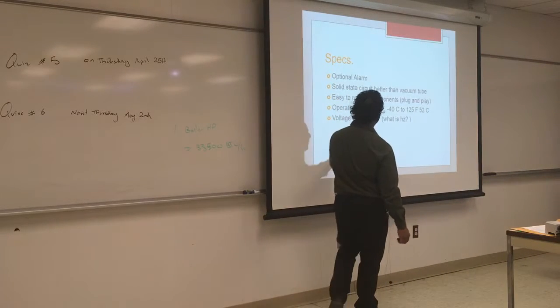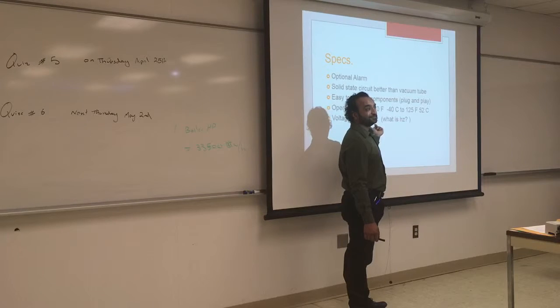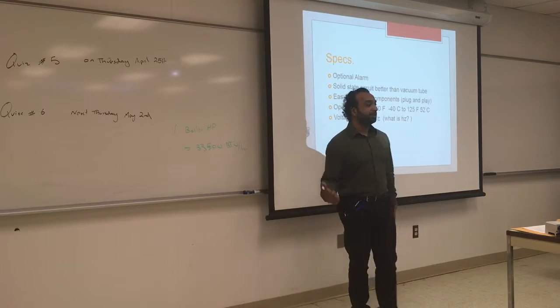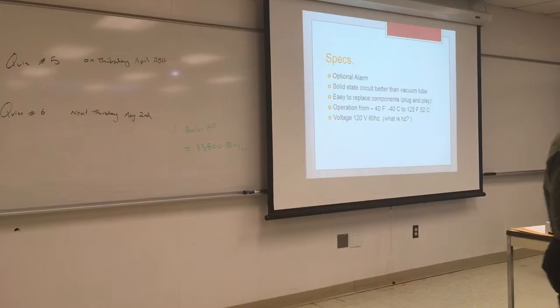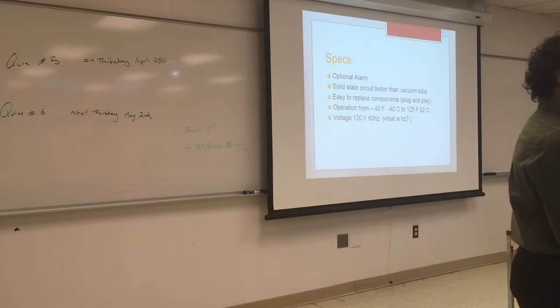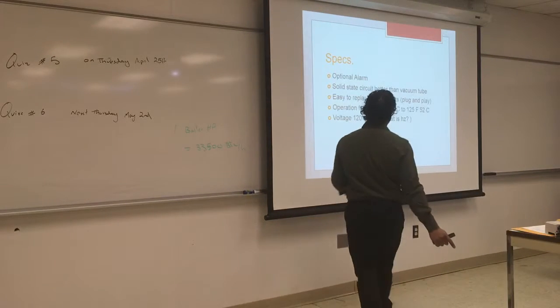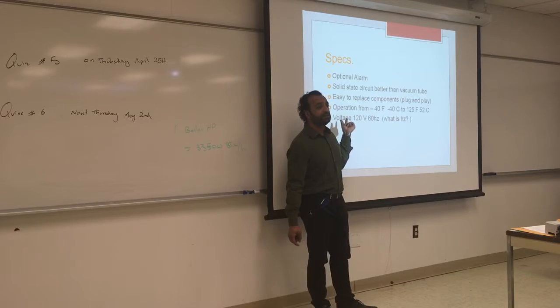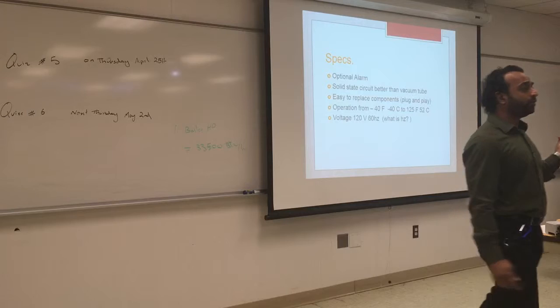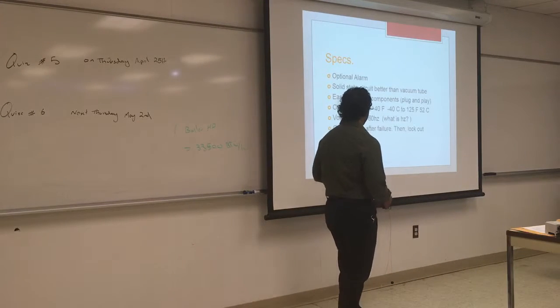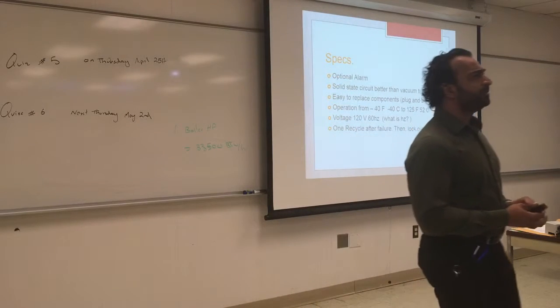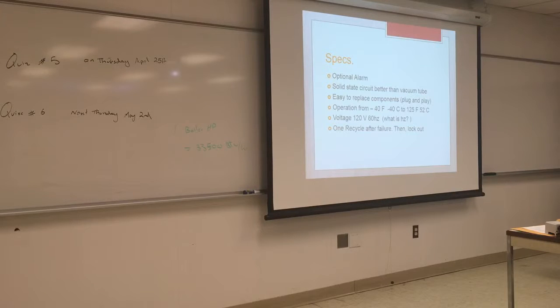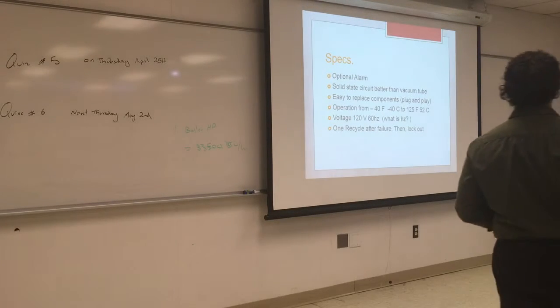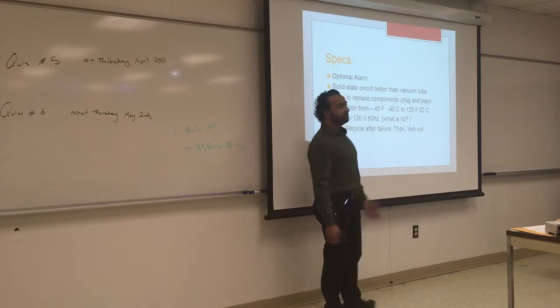The voltage is 120 volts, and I hope by now you know what hertz is. How many cycles? Yeah, it's frequency. And what frequency do you get in the residential? No, we're supposed to be getting like 60 or 59. But it can be within 10% of that in either direction, it still works, right? No, these are actually more sensitive. I don't think it's going to be more than 10%. These controls, because they're electronic and they have a lot of semiconductors, are very sensitive to frequency. If you change the frequency, it might not work properly. So we want it to be 60 hertz, and I think whether it's 10% or maybe less than that, every control is different. But from what I last checked, it was like 5% below and above. They have one recycle per failure, then it locks out.